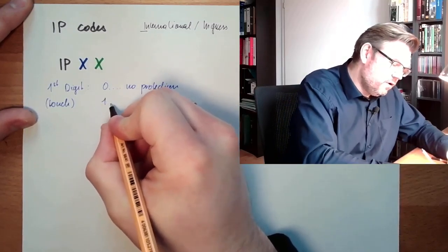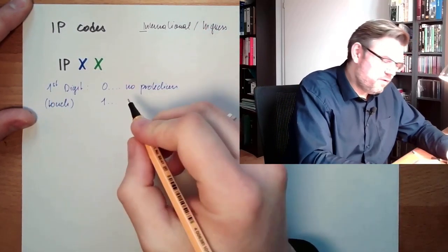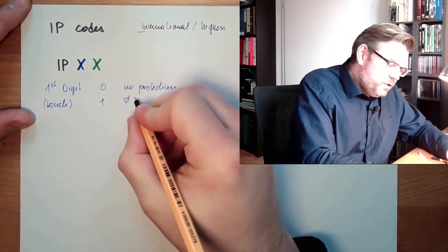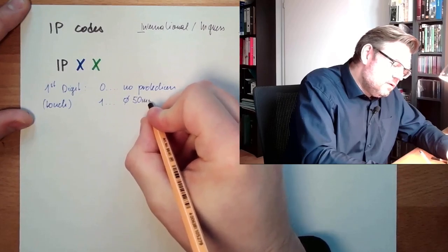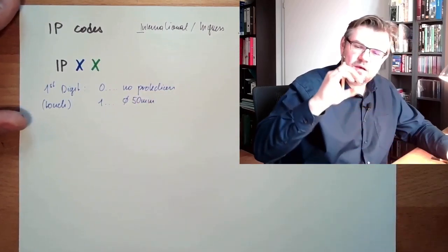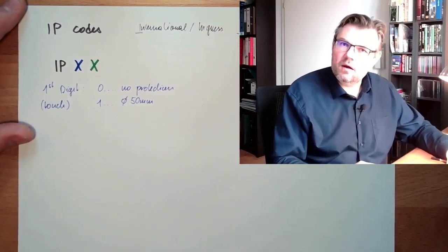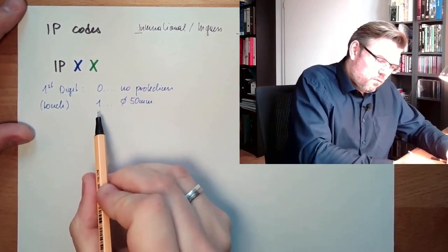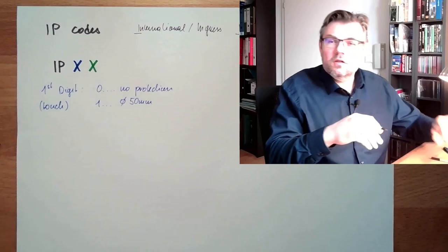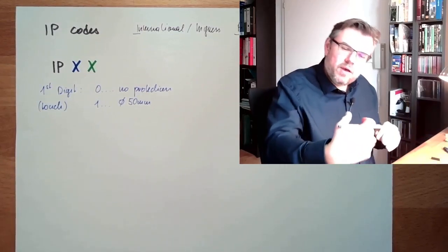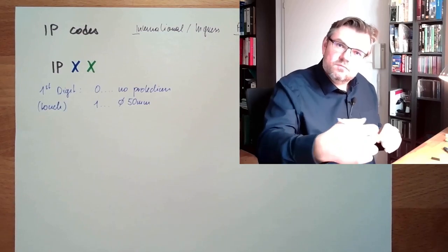If there is a one, IP one whatever, then we are protected for elements which are thicker than 50 mm. If you have something which is thicker than 50 mm, you cannot reach the electrical part. Usual thing is the back of your hand. So with the back of your hand, you're protected.